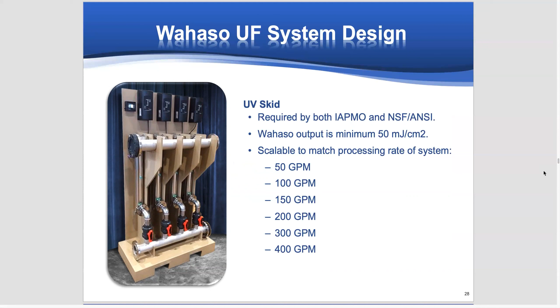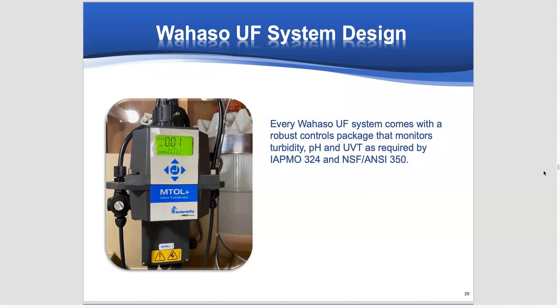We are required by IAPMO and NSF to monitor key parameters of the harvesting system. And those can usually include turbidity, pH, and the UV transmission data of how much radiation is being sent. And turbidity is our best indicator that the system is working properly, and we want to see that it is below 0.3. As I said, we're allowed to go up to 2.0, but we want to stay well below that. So when our systems run, they're typically less than 0.3 NTUs, and sometimes they're down to 0.01. It just depends on what we're doing. Next.